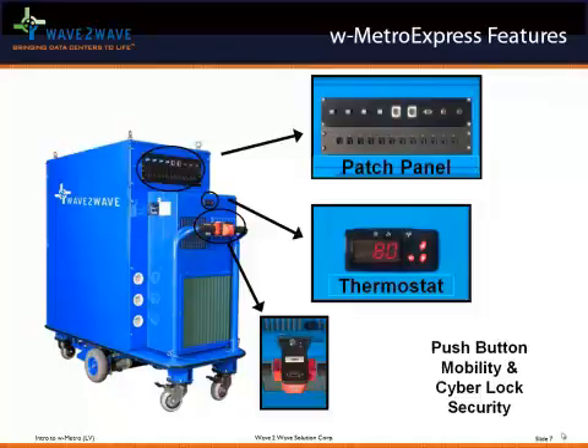The thermostat shown here allows you to adjust the temperature of the equipment inside. For example, you set the temperature at 80 degrees, and your equipment runs at a comfortable 80 degrees. If utilization increases, it becomes hot and heat rises above the 80 degree threshold. At that point, the air conditioner kicks in, brings the temperature back down to 80 degrees or less, and then backs off the power used to cool the equipment.